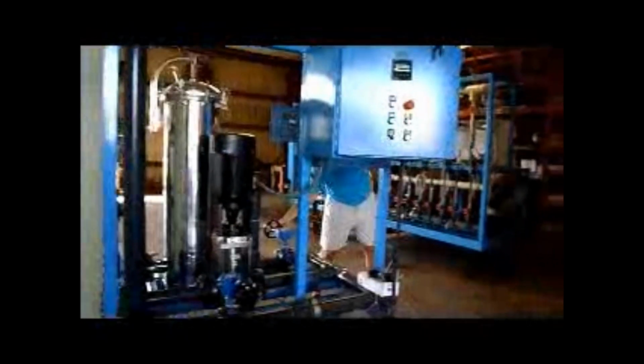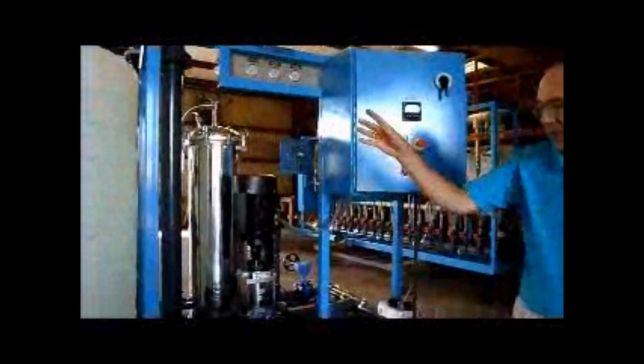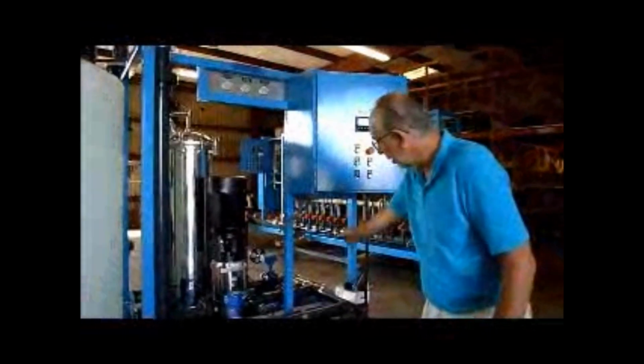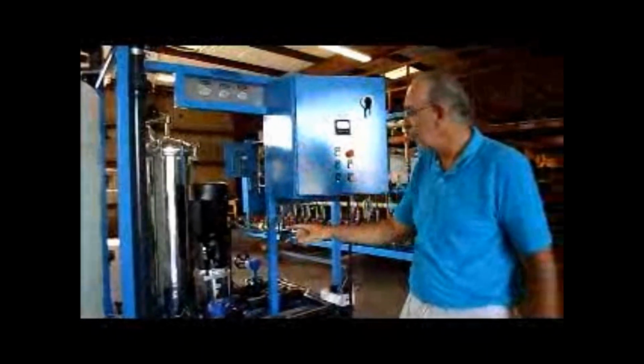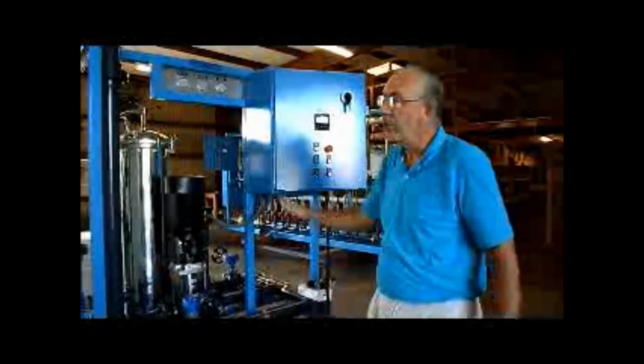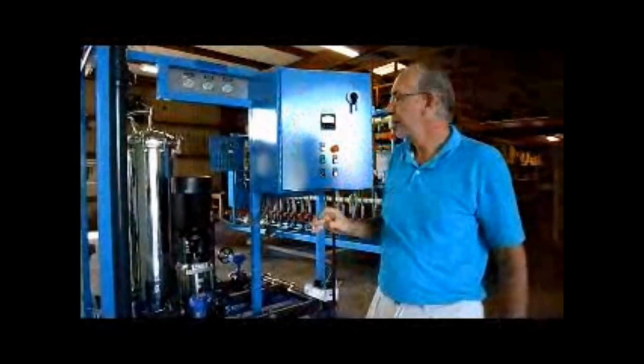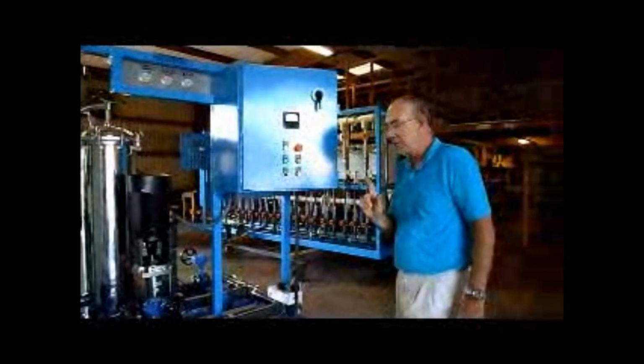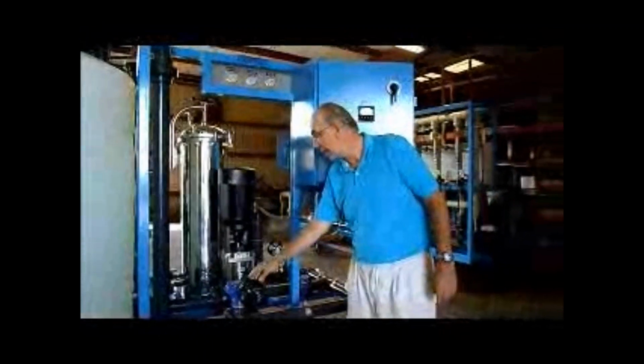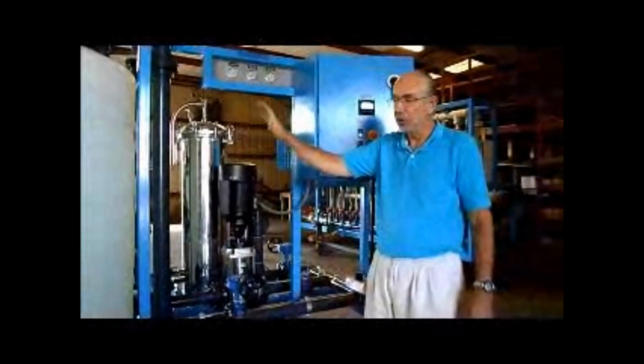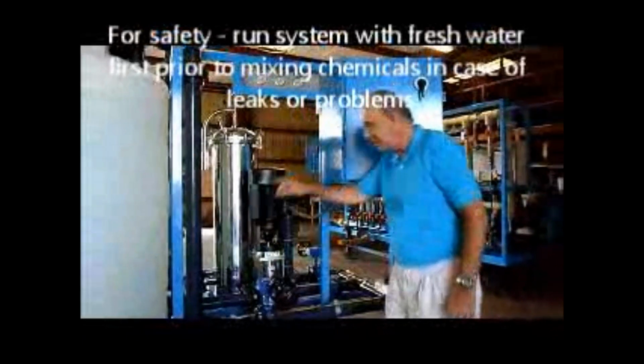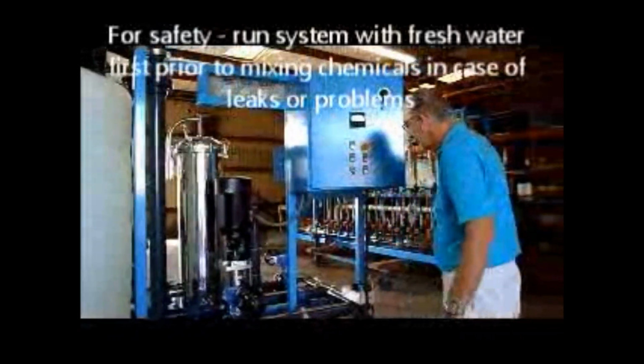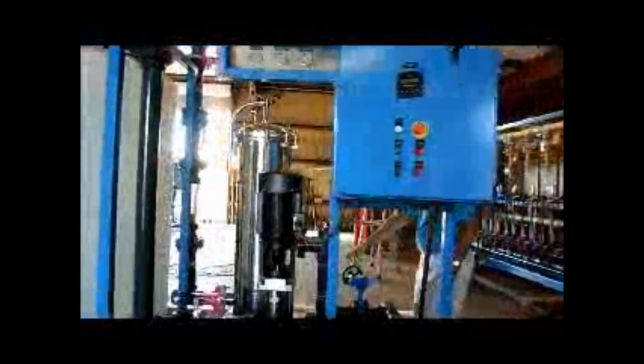The reason we do that is because we want to mix our chemicals up, and we want to make sure, by just recirculating back into my tank, mix our chemicals up and make sure everything is working okay before we start pumping solution back out to the RO skid. I recommend, just for safety purposes, since some of these cleaning chemicals are hazardous, at first just fill it with water, permeate water. Close that, open this, circulate back through, make sure everything's good. Then start to open this valve until you get the flow rate you want through this flow meter, get some flow. Then you can close this valve off if needed.